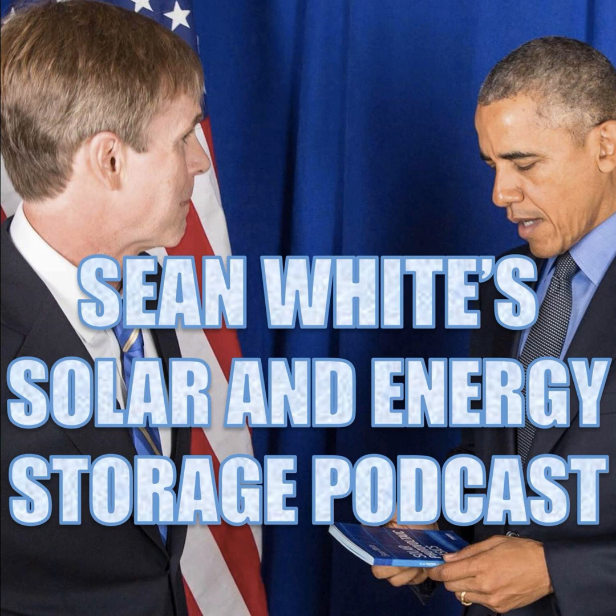Going on to 712. We're going to cover some of 712 here. Just going to give my opinion about 712. There are very few DC microgrids out there. And in the 2023 code, we're migrating all this stuff into Article 705 because we have interconnected power sources that interconnect both on the DC side and the AC side. We've seen the DC coupled battery systems. We showed that earlier, DC coupled PV with energy storage and the like. That really belongs in Article 705 because we do it all the time.